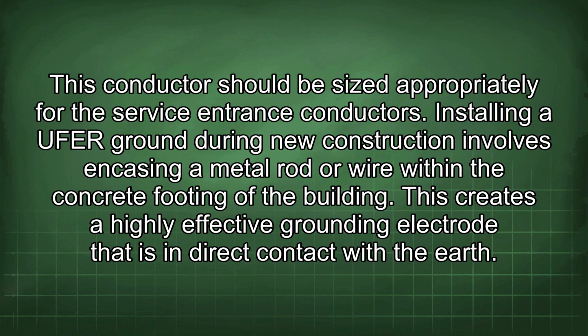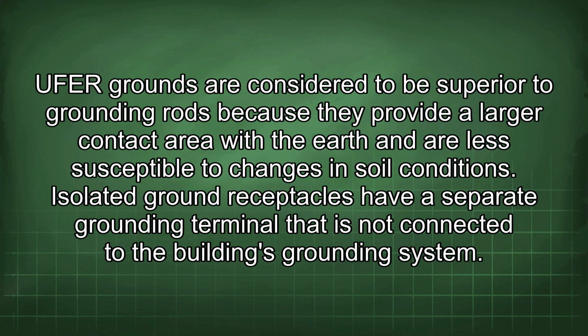Installing a UFER ground during new construction involves encasing a metal rod or wire within the concrete footing of the building. This creates a highly effective grounding electrode that is in direct contact with the earth. UFER grounds are considered to be superior to grounding rods because they provide a larger contact area with the earth and are less susceptible to changes in soil conditions.